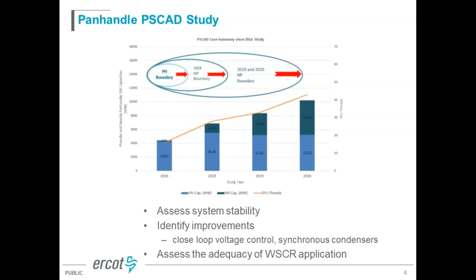As in many other regions, before considering weak grid conditions you want a tool or indicator to help identify whether the system is weak or not. In ERCOT, we have a weighted short circuit ratio application and index to help evaluate system stress in the panhandle region. To make sure that index and its application can continue to be used, we also perform PSCAD studies, comparing detailed EMTP results versus the identified threshold of the index, to confirm whether the application still fits or whether adjustment is necessary based on system conditions.